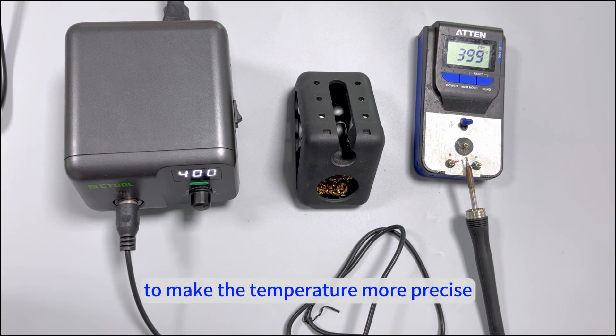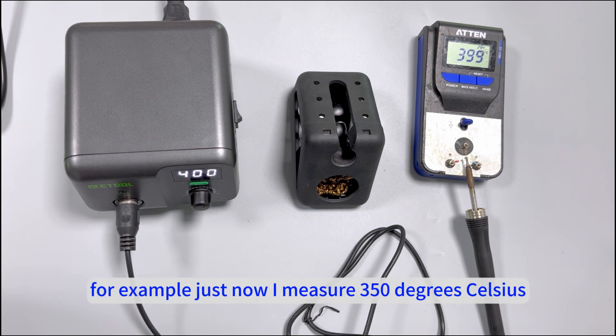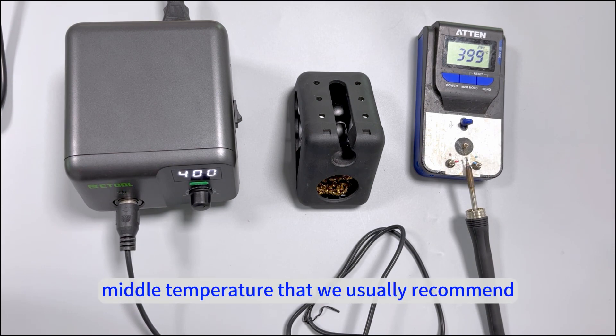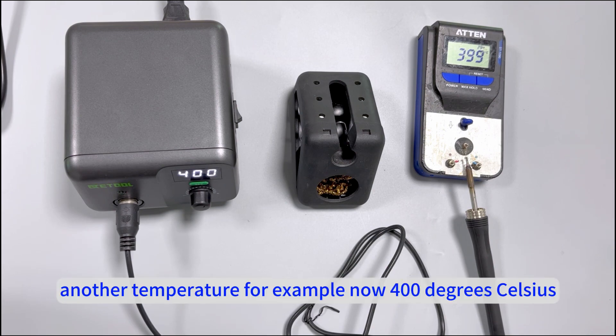So, to make the temperature more precise, we suggest calibrating the actual temperature. For example, I just measured 350 degrees Celsius, and this is the middle temperature that we usually recommend measuring. And another temperature, for example, now 400 degrees Celsius.